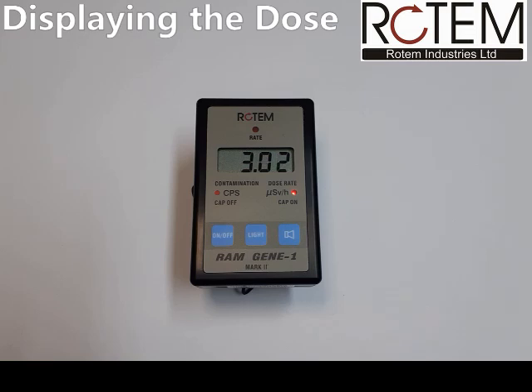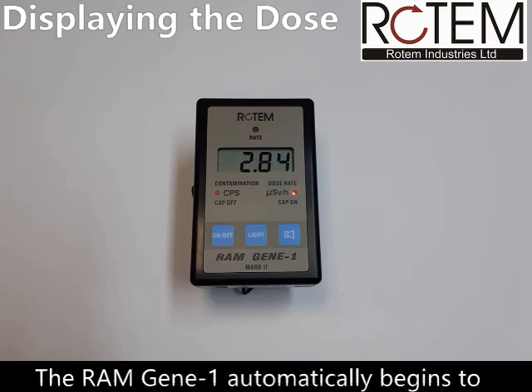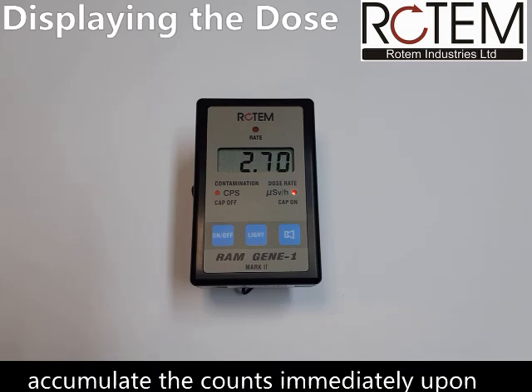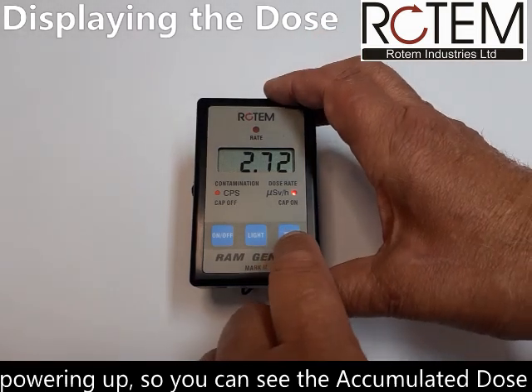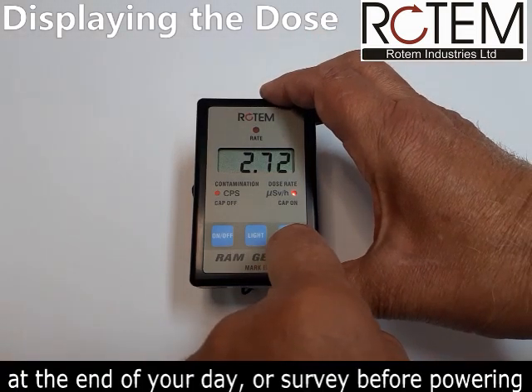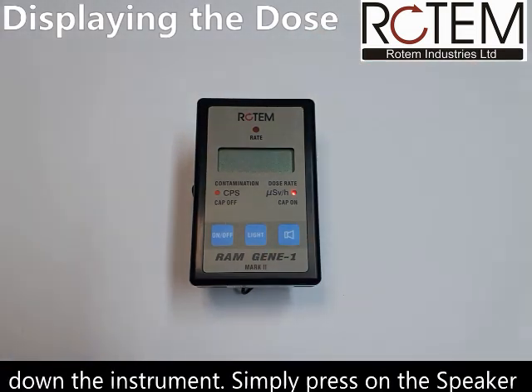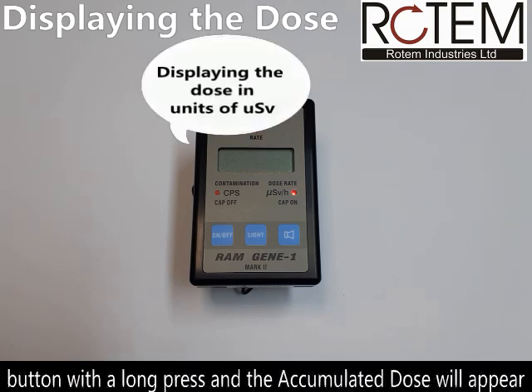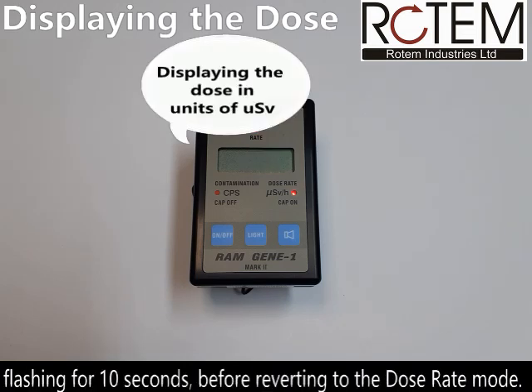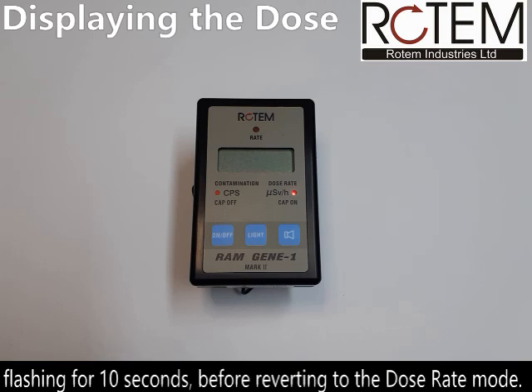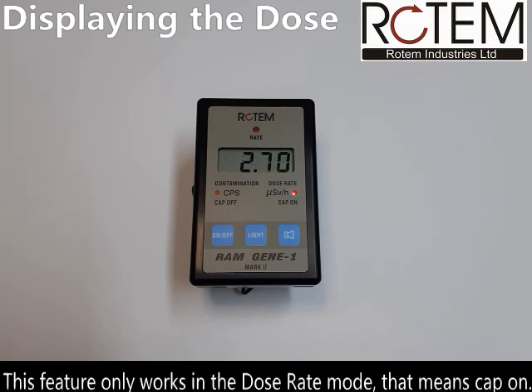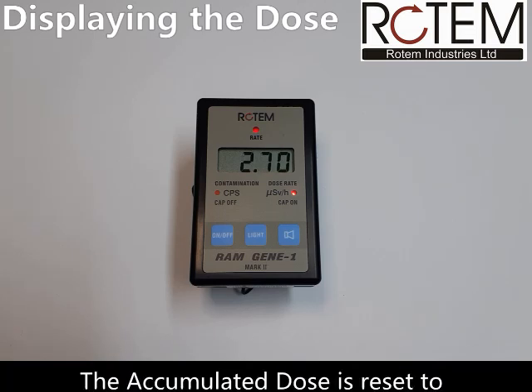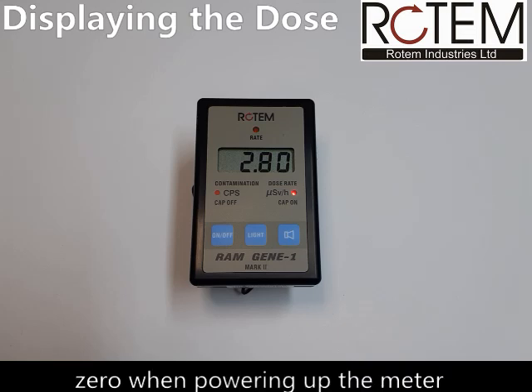Displaying the accumulated dose. The RAM Gene 1 automatically begins to accumulate the counts immediately upon powering up, so you can see the accumulated dose at the end of your day or survey before powering down the instrument. Simply press on the speaker button with a long press and the accumulated dose will appear, flashing for 10 seconds, before reverting to the dose rate mode. This feature only works in the dose rate mode. That means cap on. The accumulated dose is reset to 0 when powering up the meter.